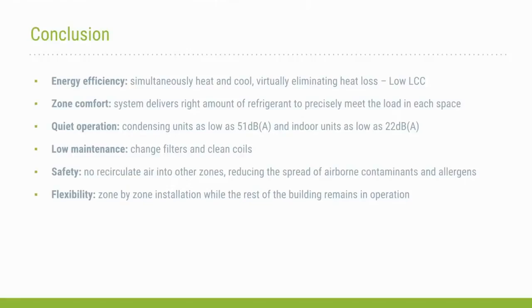For safety in a courthouse, we're not recirculating air from one zone to another, which there are some concerns about in a courthouse for airborne contaminants and allergens. And the flexibility that we gained, especially during this install, was able to go zone to zone and do in-zone work while the rest of our building remained in operations. It was really quite a sight to see, and we have quite a bit of photos that we could share at another time of how we did that, and were able to return a space to full operation for a client like the U.S. Attorney's Office or the U.S. Marshals during an overnight, and they had full operation of the space during the day. So that is very positive for us.